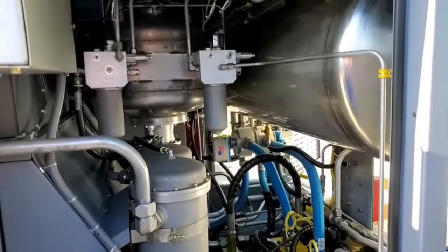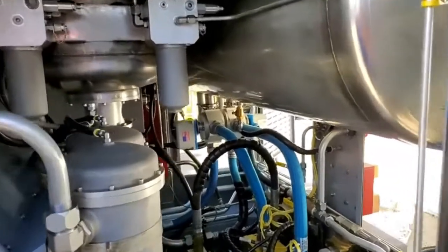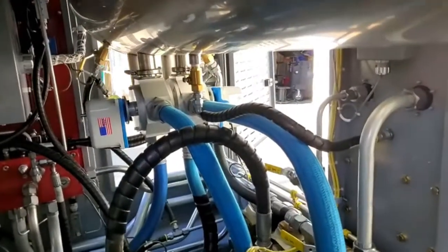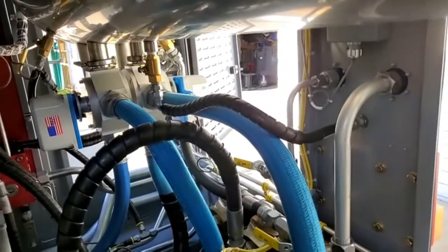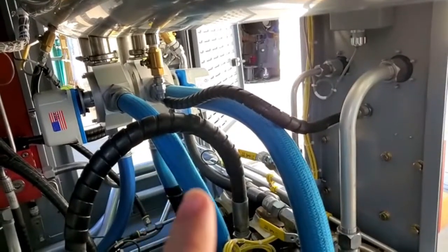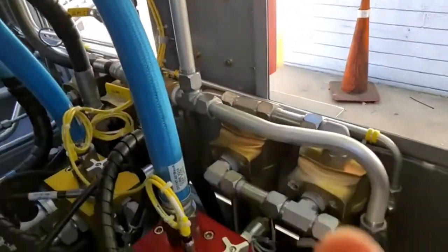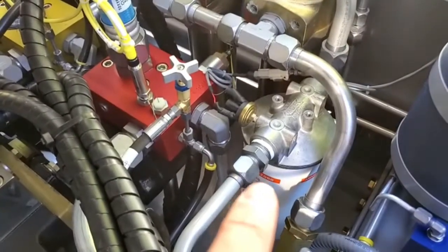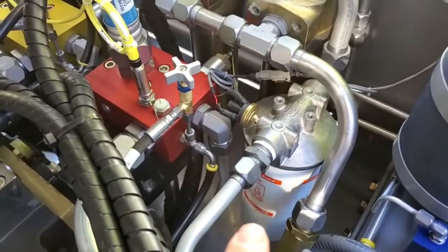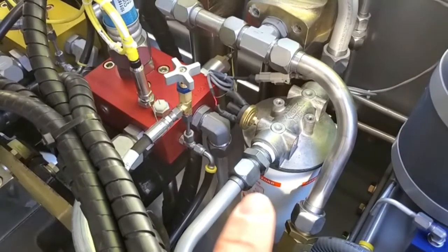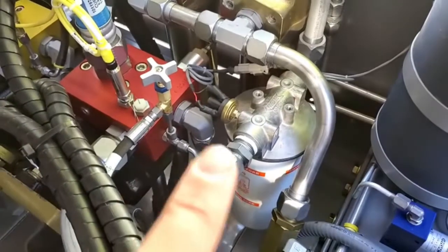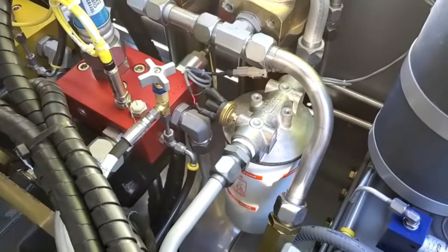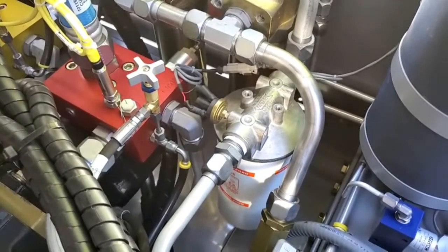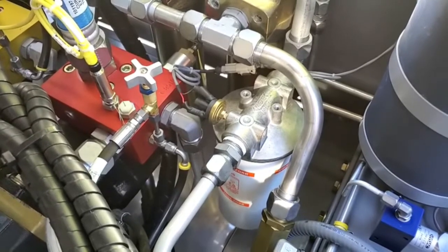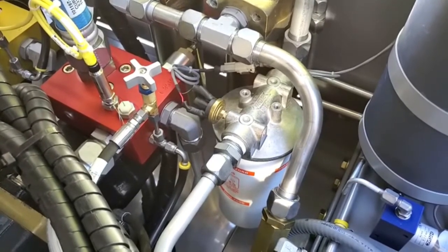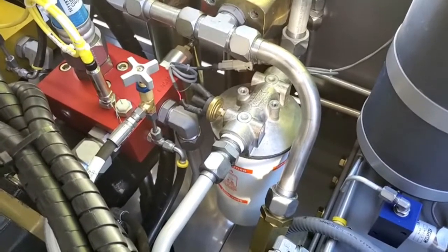I'm going to discuss purification system operation. So the valve on the far side should be open, and you'll feed along this black tube hose right here, along this line down to moisture separator filter 1. This is a spin-on filter which removes moisture from the fluid. This switch here is a negative pressure switch. So if it draws a vacuum of about 10 inches of mercury, that switch should close and provide an alarm telling you that you've got moisture separator filter 1 clogged.